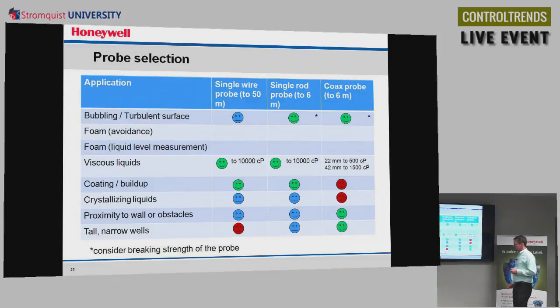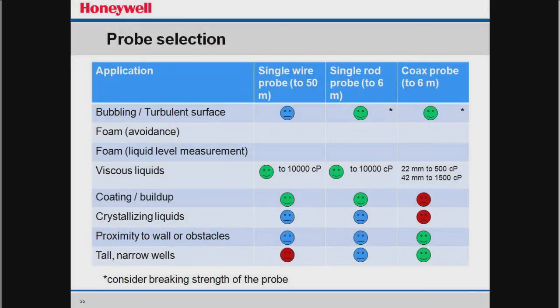And here's a comparison. Really what I want to highlight is with the coax, we want to make sure that it's a clean liquid. We're not going to have problems with bridging. And then on the single wire, what we're saying is that for tall, narrow wells, you want to be careful with a single wire. So why do you think that would be? So let's say it's a long well going down there. You've got a cable probe down there with the weight on the end of it. What might be a concern with that? Exactly. That would move within the stilling well, and wherever that cable touches the wall of the stilling well, you're going to get a reflection, and that's not going to be the reflection off the surface.